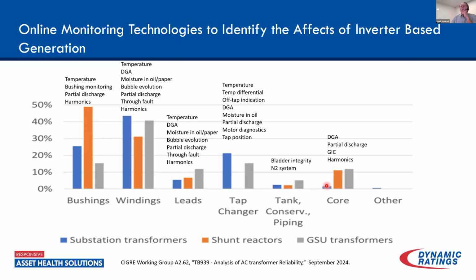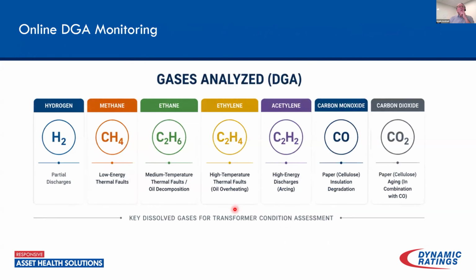And when it comes to generation activities, GIC may or may not be an issue for you. It really depends on the length of the transmission lines and stuff like that. So when we look at those monitoring technologies, some type of online DGA is pretty much always recommended. At a minimum, you're going to want a key gas monitor doing hydrogen, or possibly hydrogen and carbon monoxide. Key gas can also do hydrogen, acetylene, and carbon monoxide, in addition to the moisture. Many renewable providers are focusing more on the multi-gas monitors, so they can get additional information and better assess in real time what's happening on their transformers.